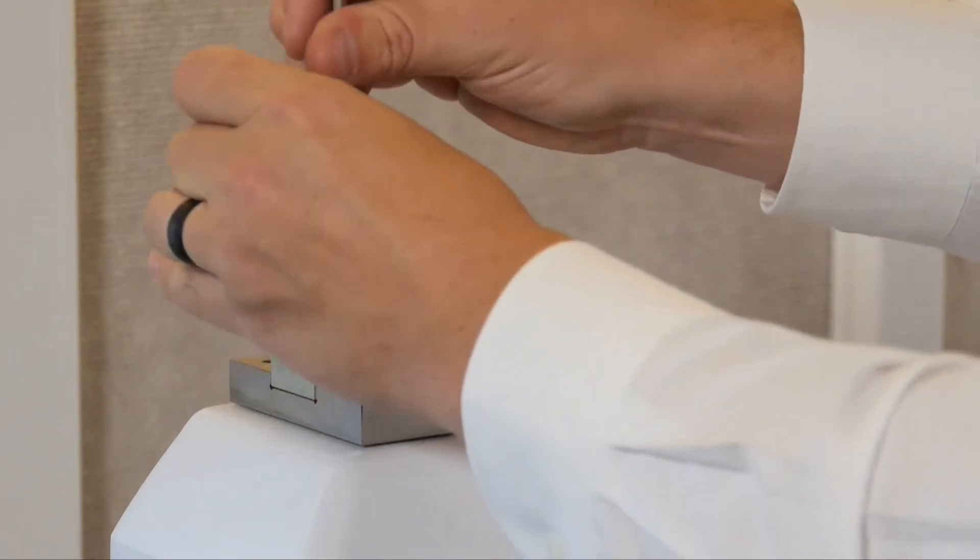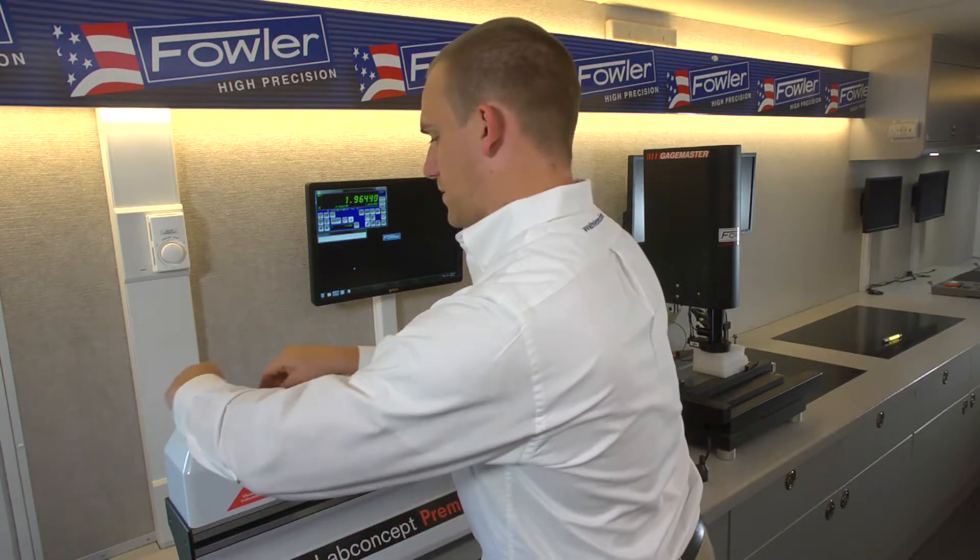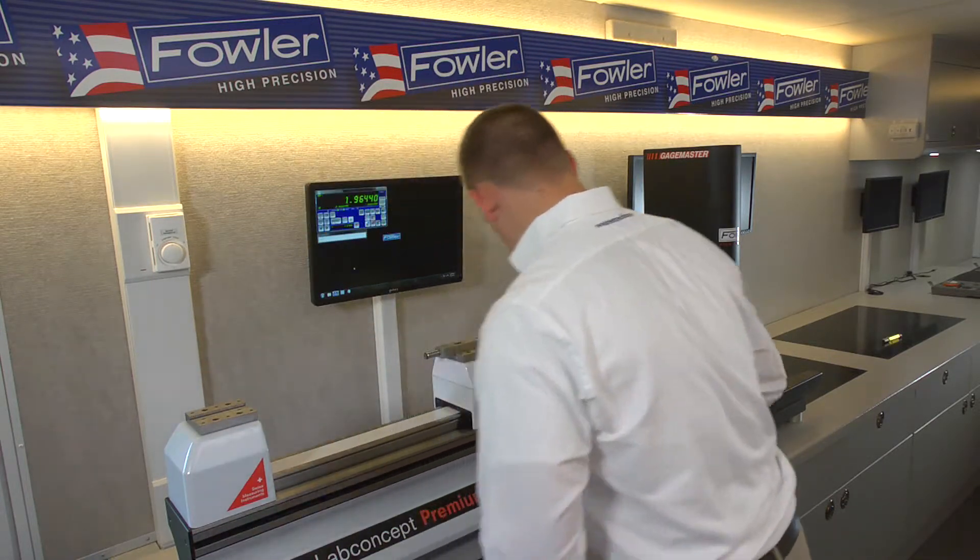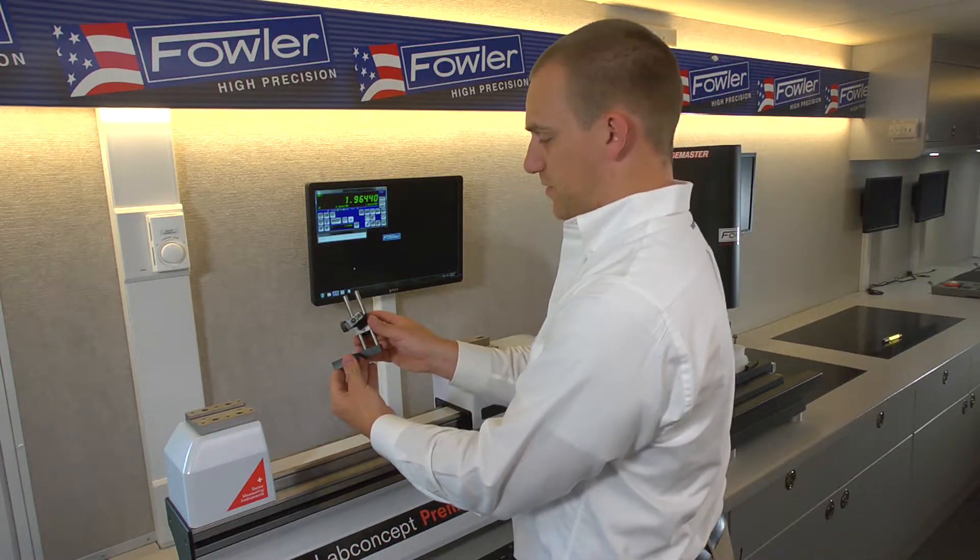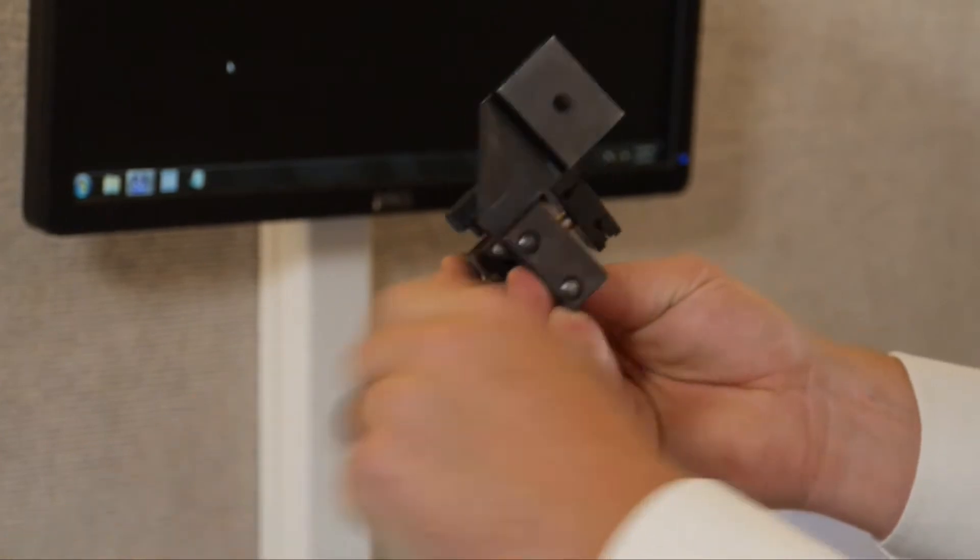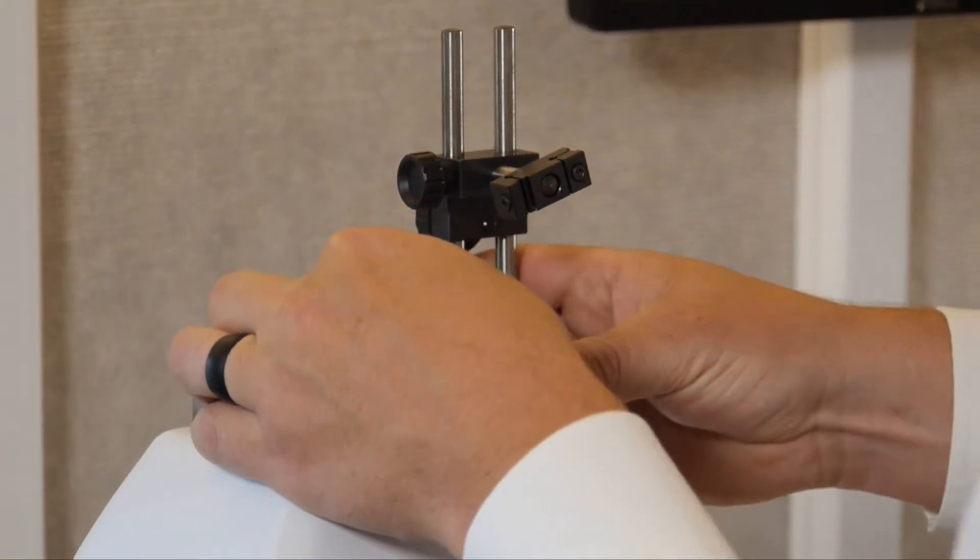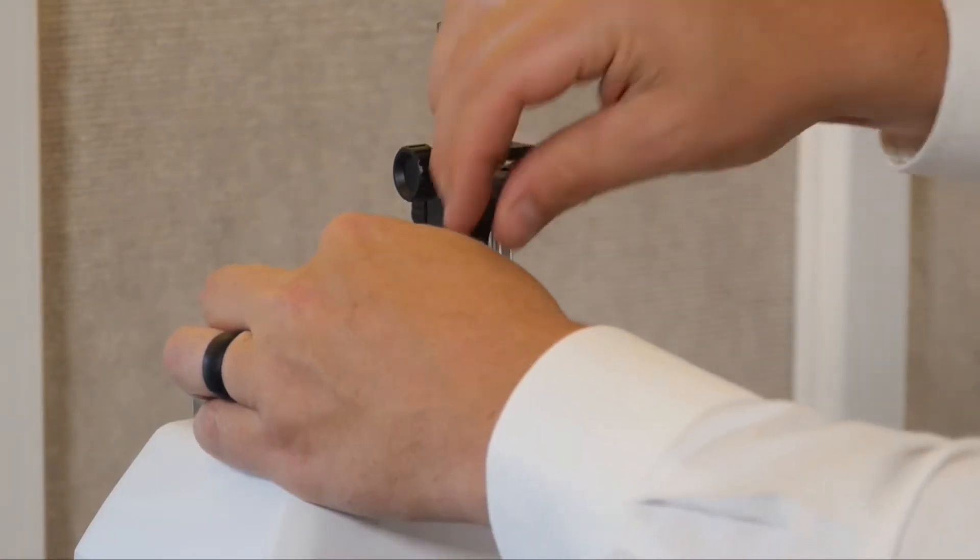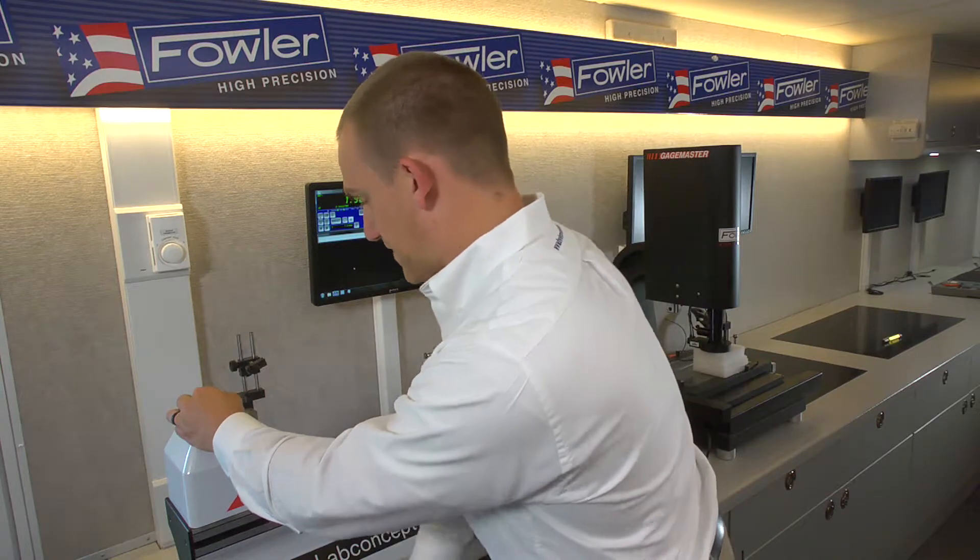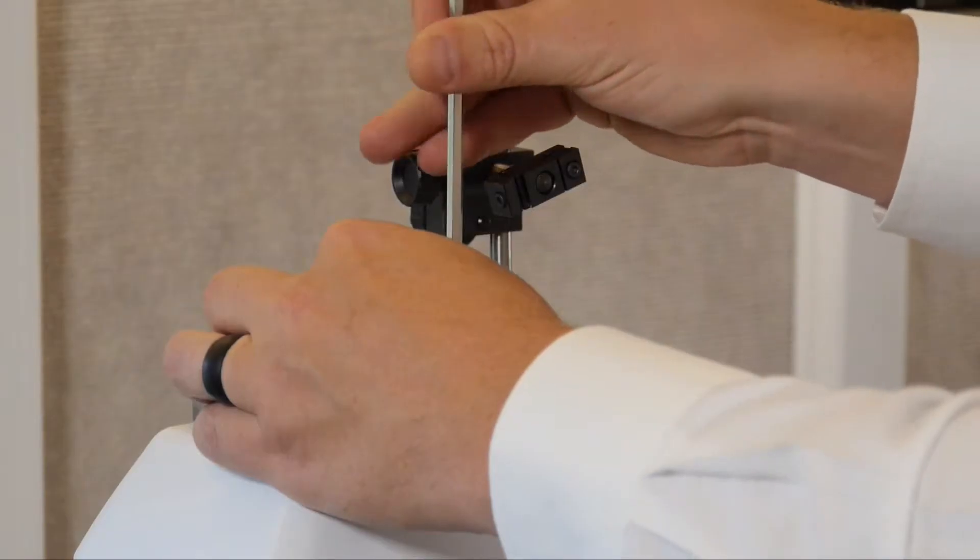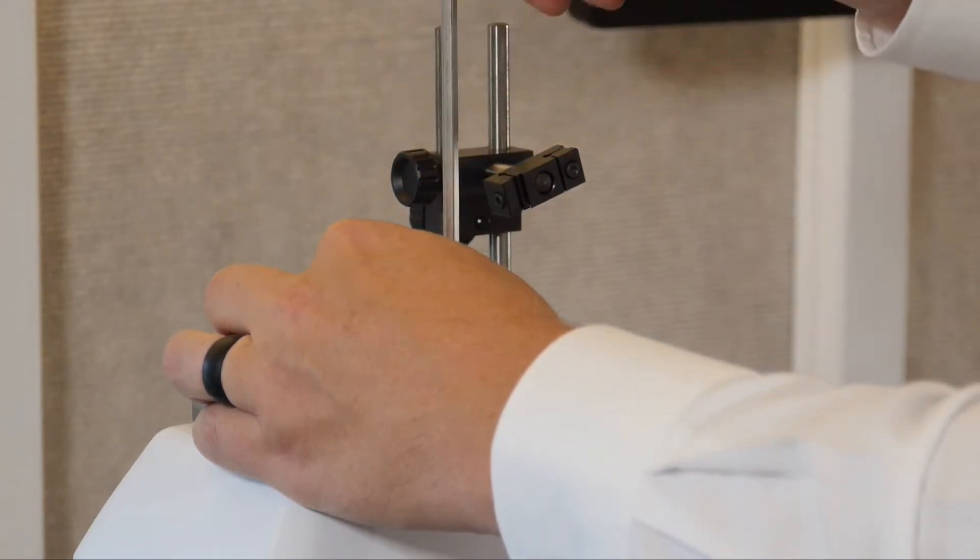We'll pull these screws right out and then we have our fixture for holding test indicators here. You can see there's this block which fits in place of the anvil. Use one of the same screws to fasten that in place and make sure it's good and snug.